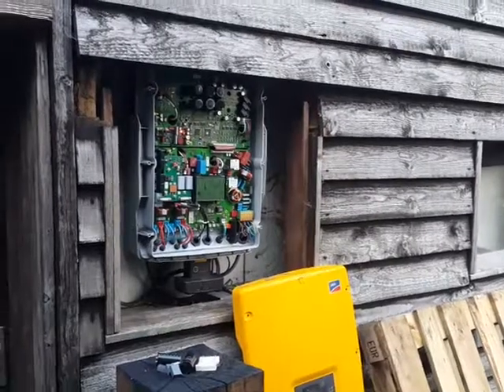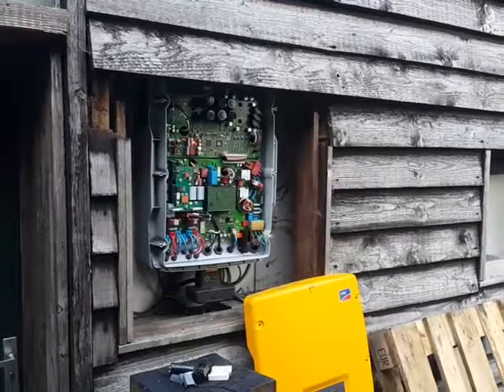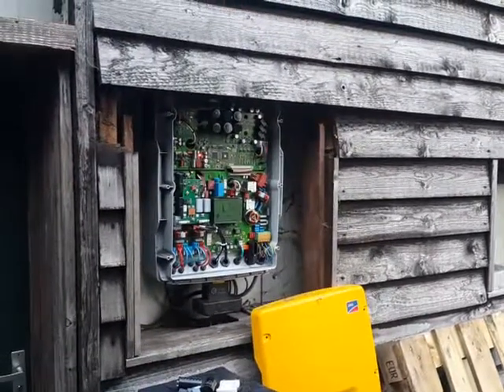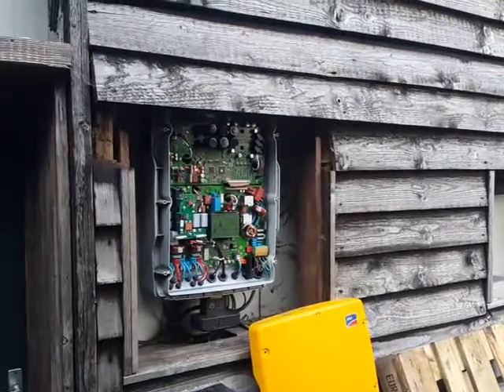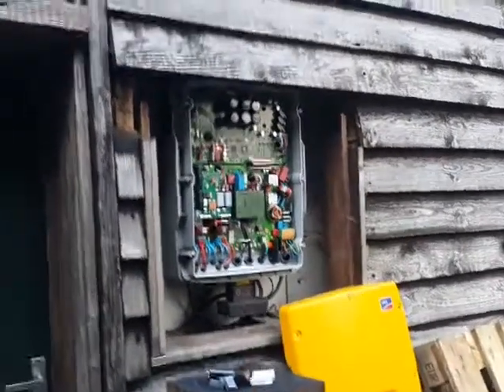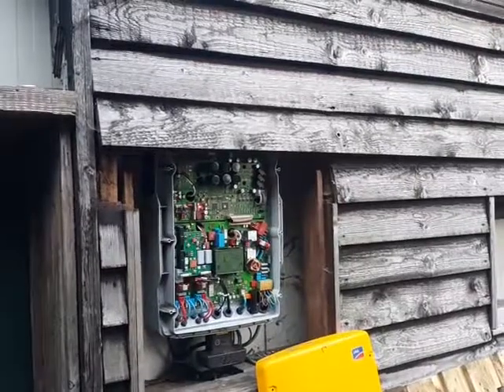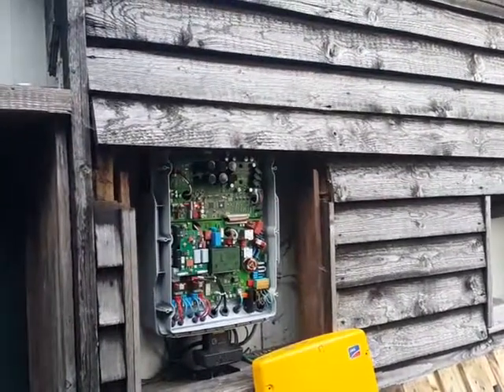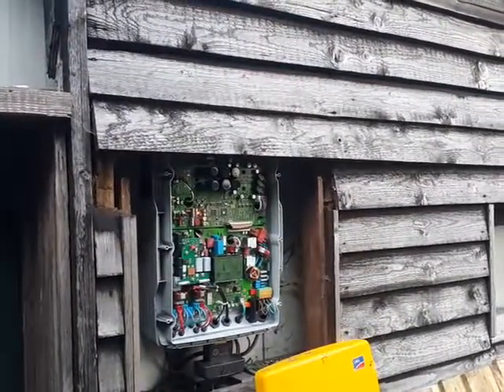Hello, this is the second video of the repair of the solar inverter SMA Tripower. The error shown was 6408, and according to the service manual, the reason is called UCE monitoring. Mysterious error.